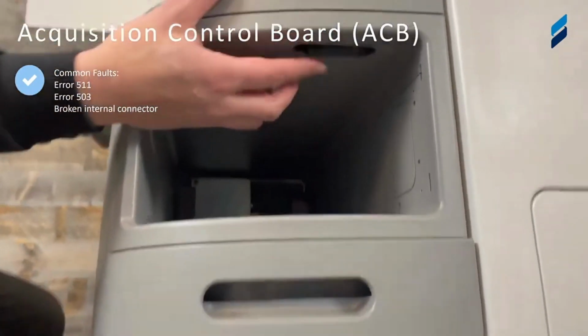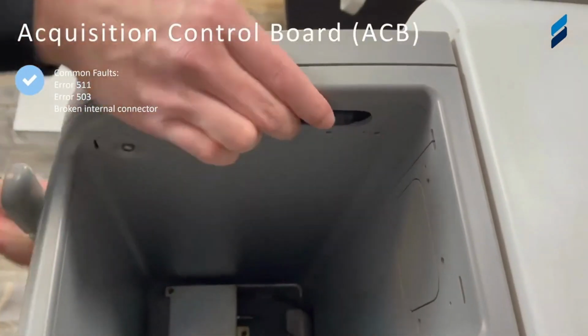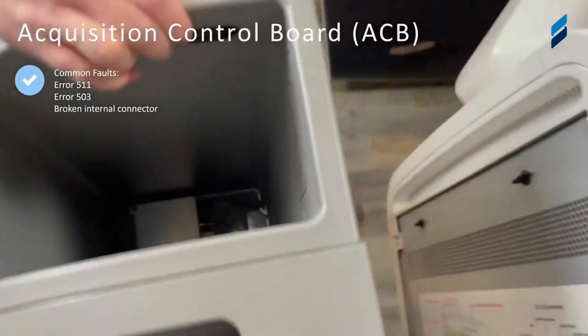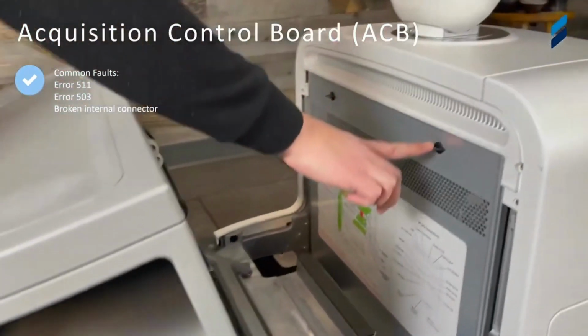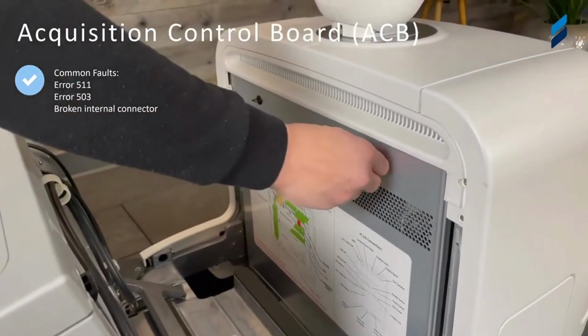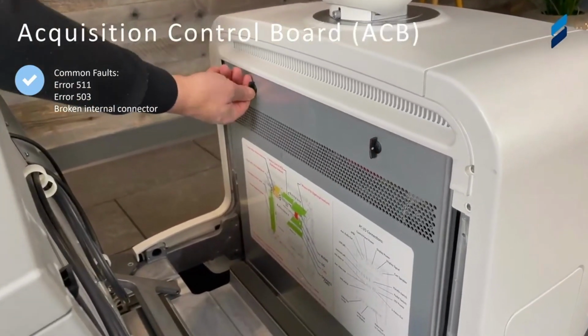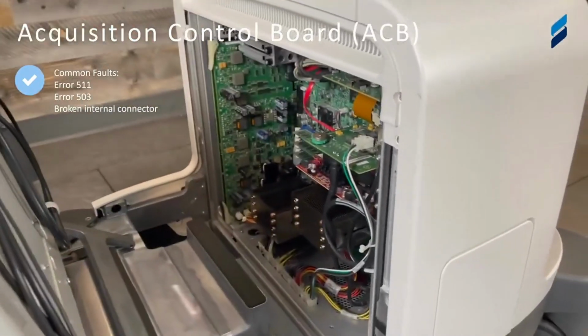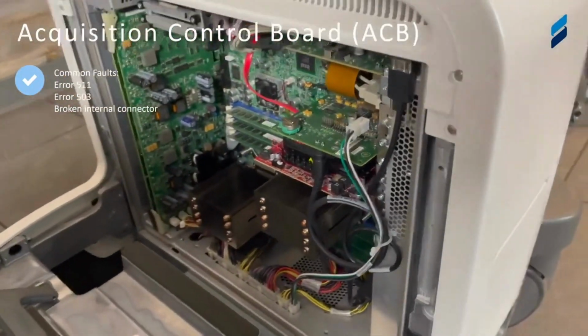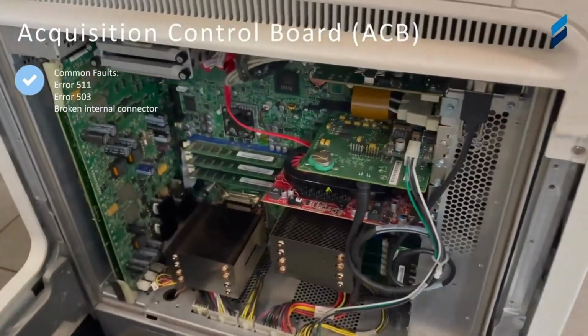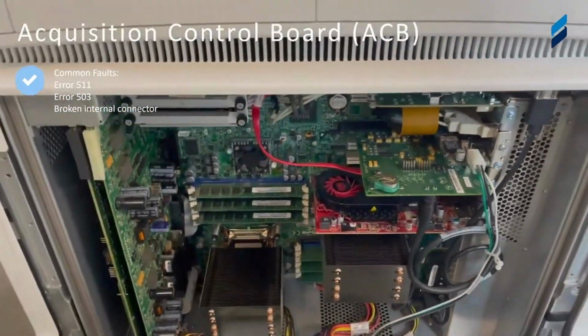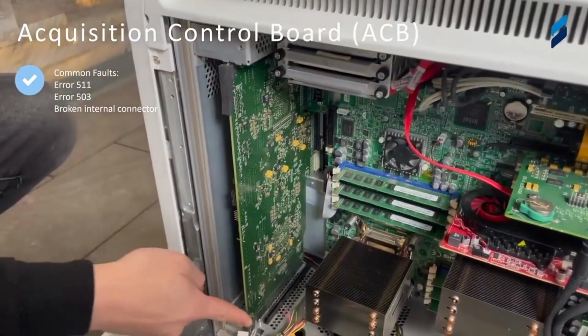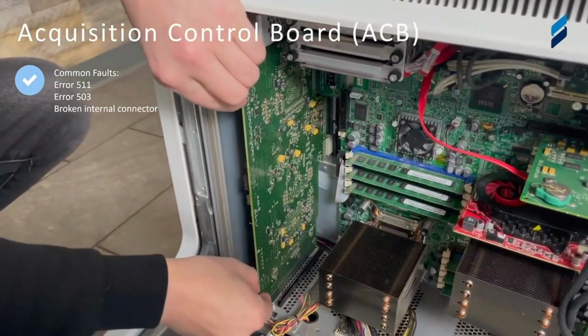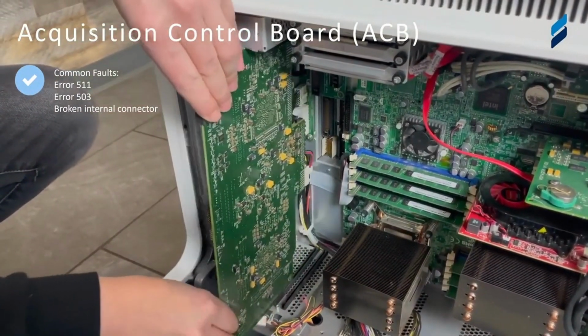All right, we're going to jump into an acquisition control board. This board is one of the boards that directly connects to the acquisition module. It is a fairly common failing board. Some common faults we've seen are 511, 503, and some broken connectors here and there. It is the board that's next to the power regulator board inside the Ebox. And we are going to show you that it's the left card out of the two.